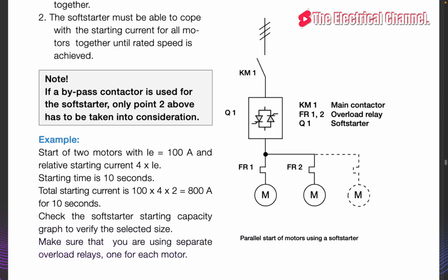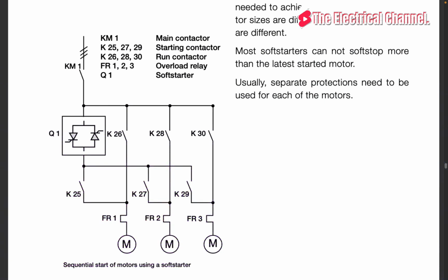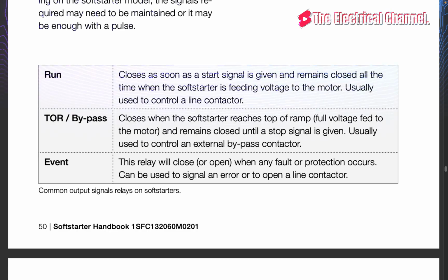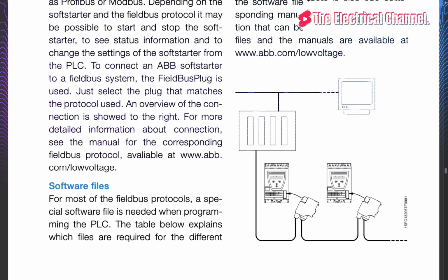In some applications where the overload protection is bypassed, all the protection is active during start. To achieve a longer reliable start time, it is particularly important to check the soft starter starting capacity, since this will be the limitation.